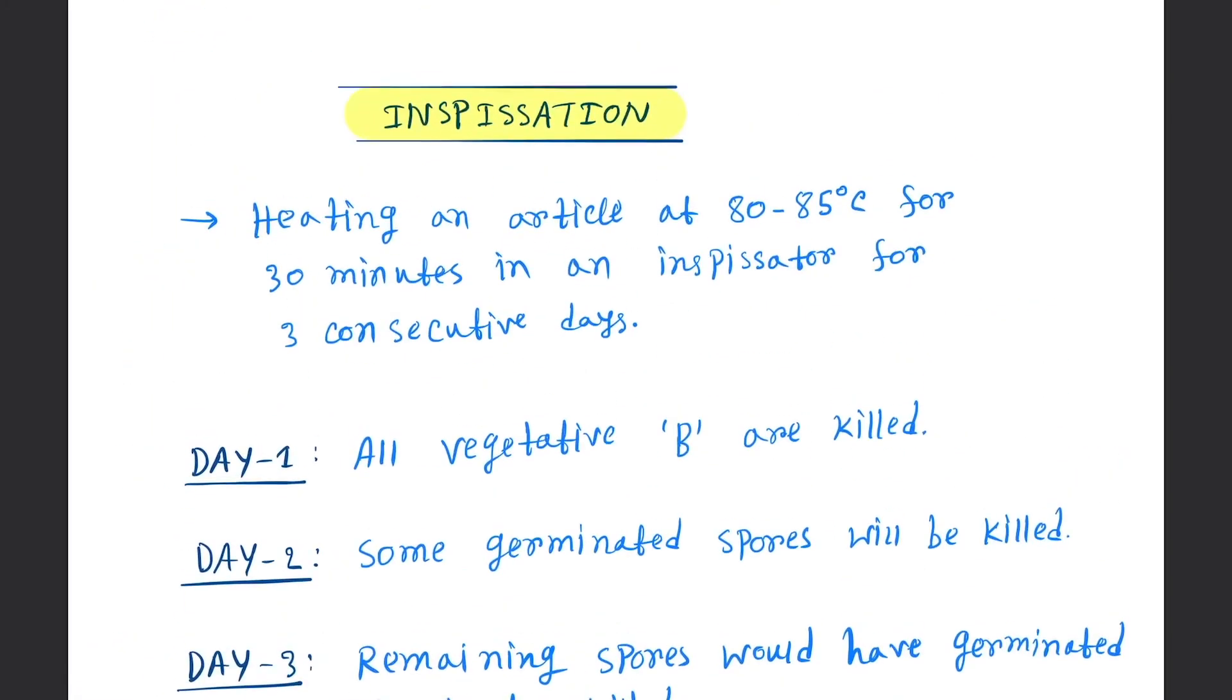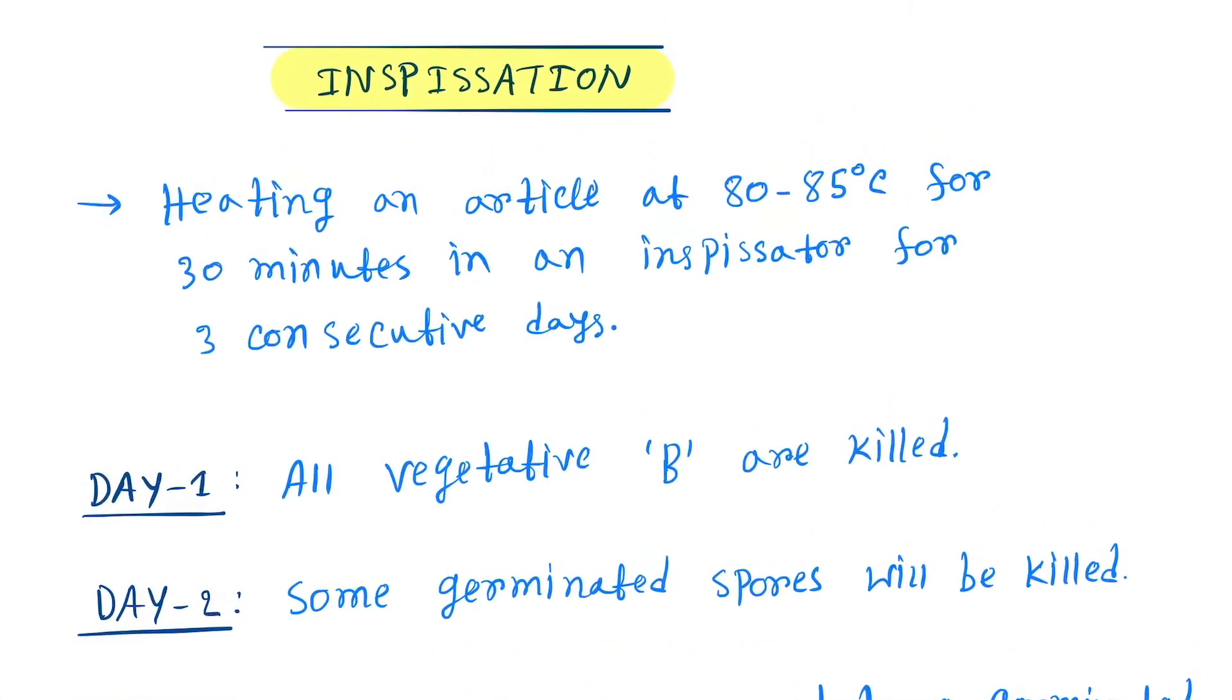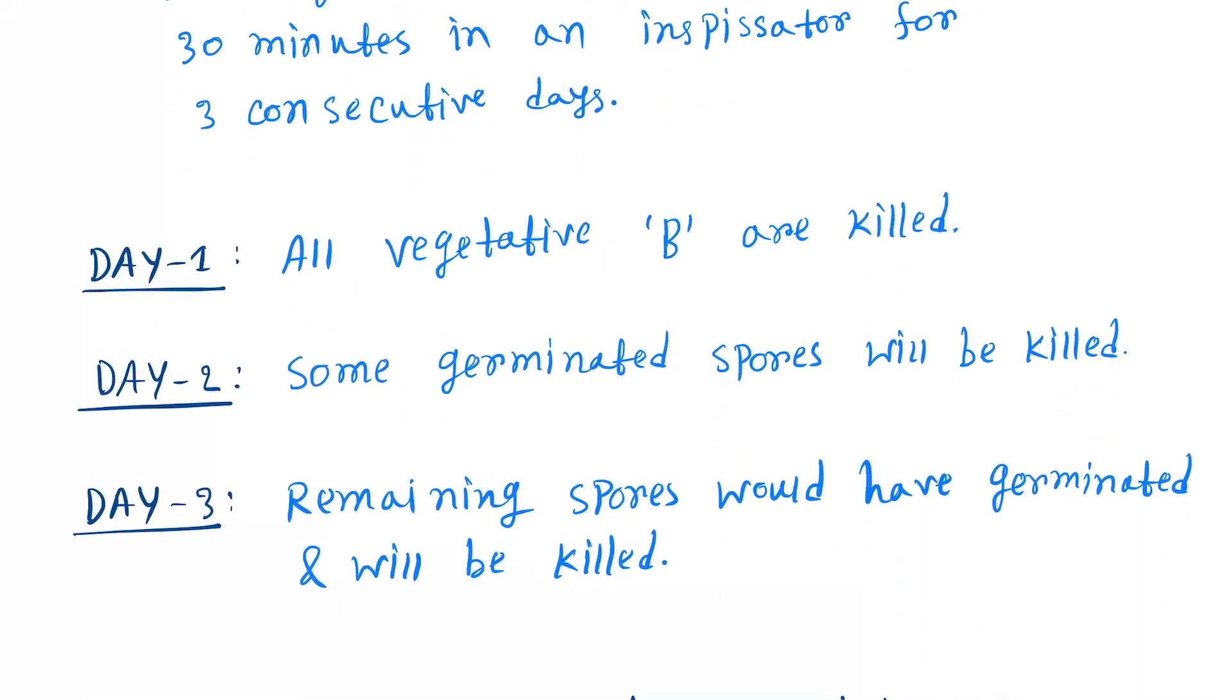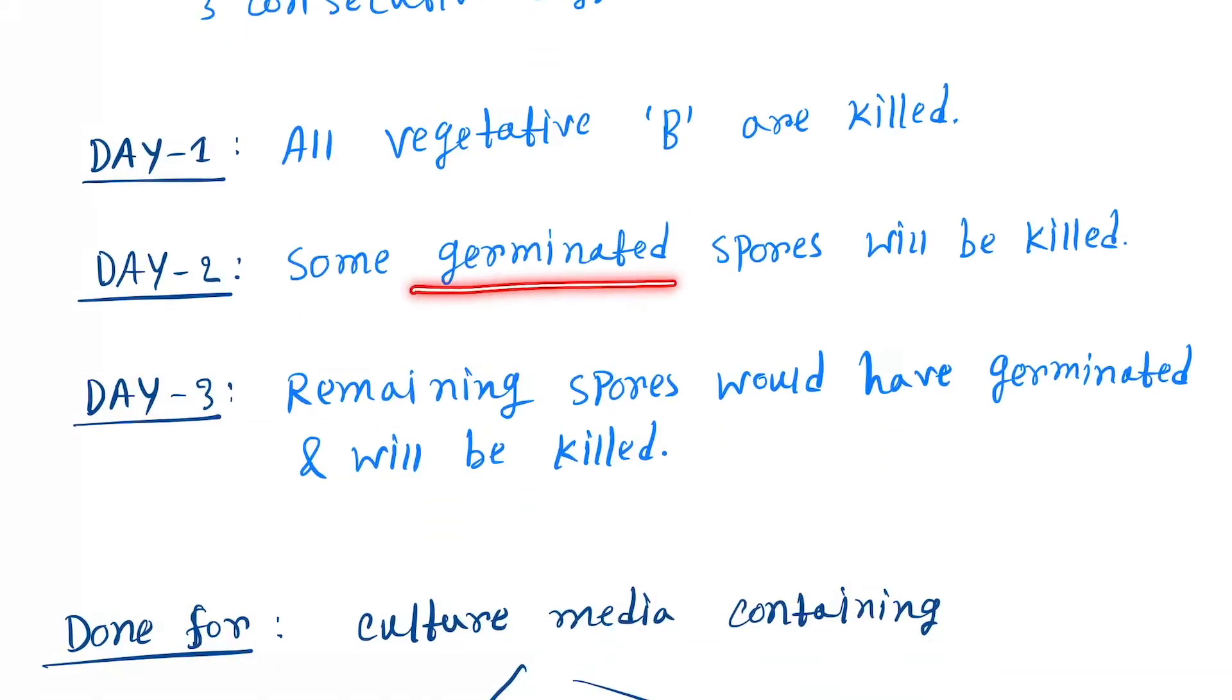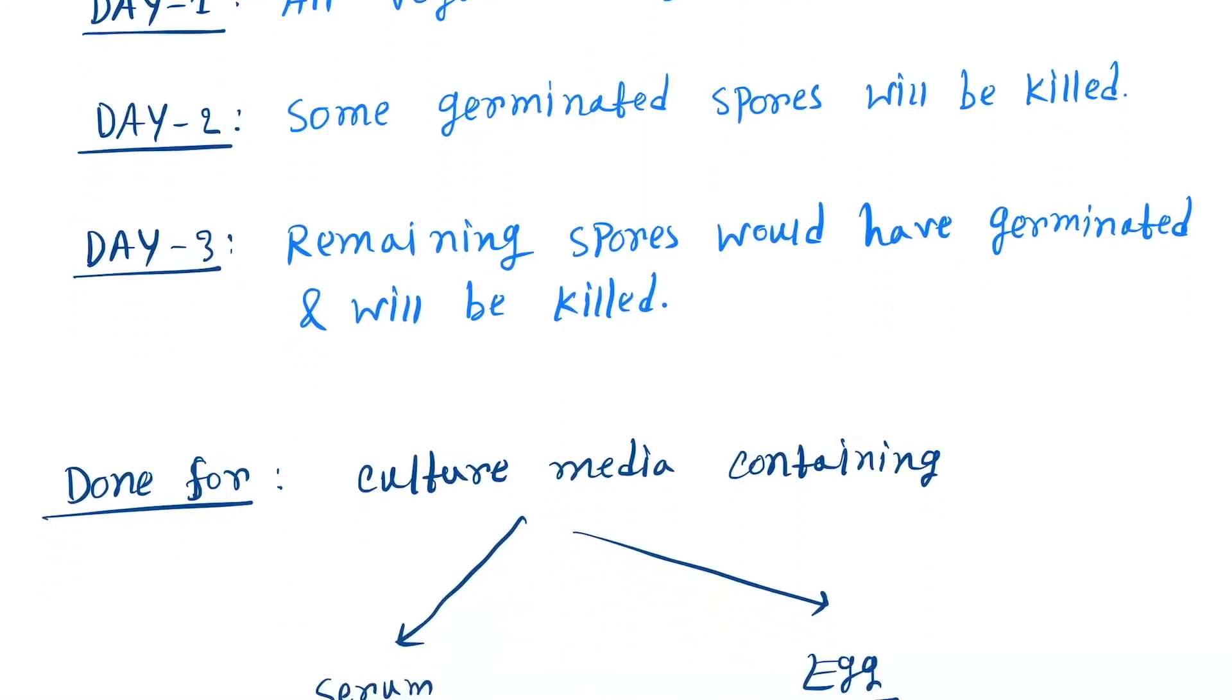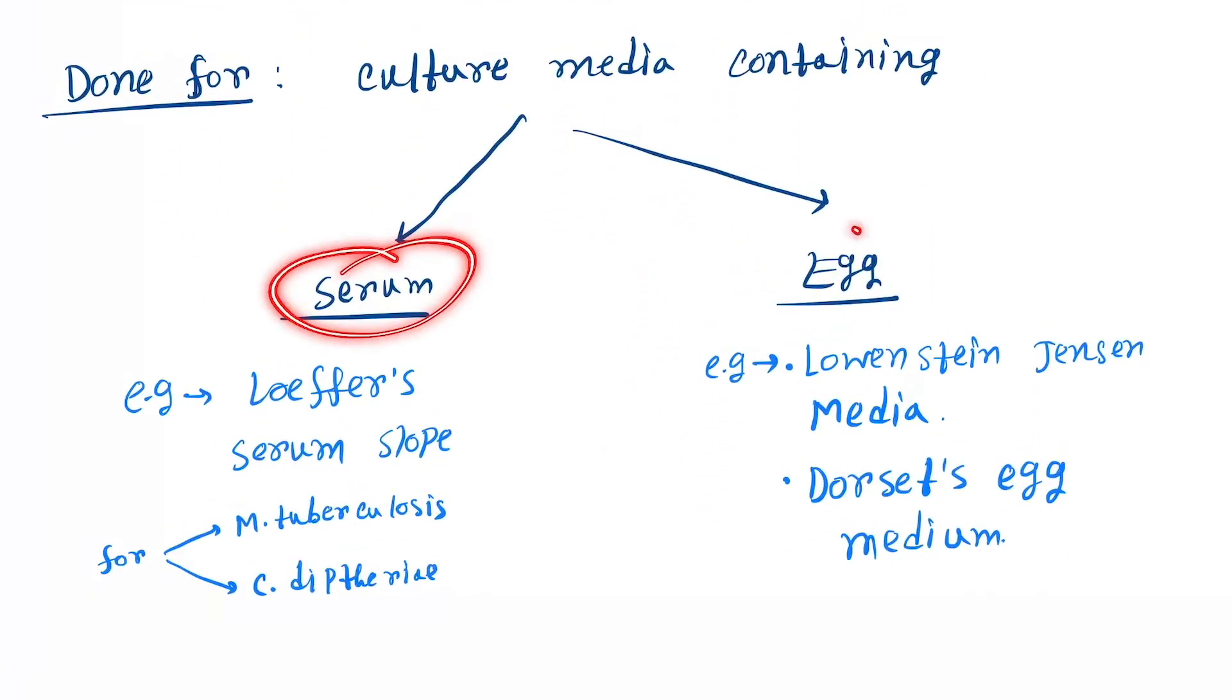Let's see inspissation in detail. Heating an article at 80 to 85 degrees Celsius for 30 minutes in an inspissator for three consecutive days. Day one: all vegetative bacteria are killed. Next: some germinated spores will be killed. Remaining spores would have germinated and will be killed. Done for culture media containing serum and egg. Serum-containing media like Loeffler's serum slope, and egg-containing is Lowenstein-Jensen media and Dorset egg medium.